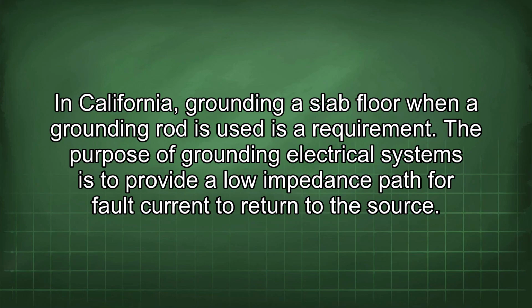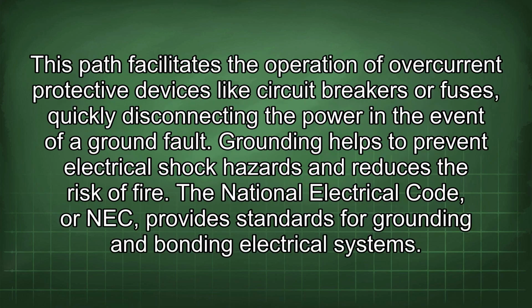In California, grounding a slab floor when a grounding rod is used is a requirement. The purpose of grounding electrical systems is to provide a low impedance path for fault current to return to the source. This path facilitates the operation of overcurrent protective devices like circuit breakers or fuses, quickly disconnecting the power in the event of a ground fault.